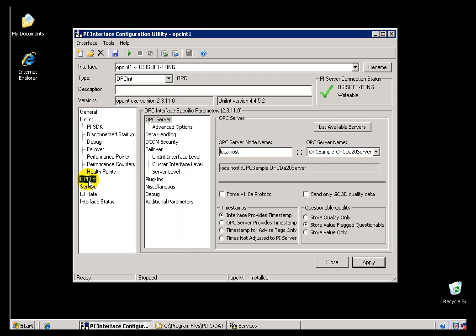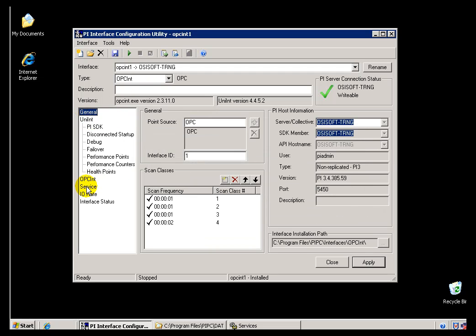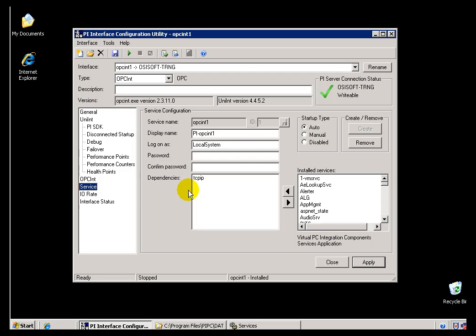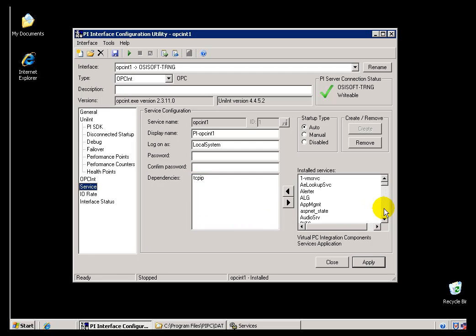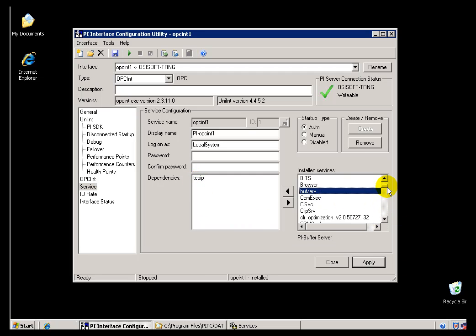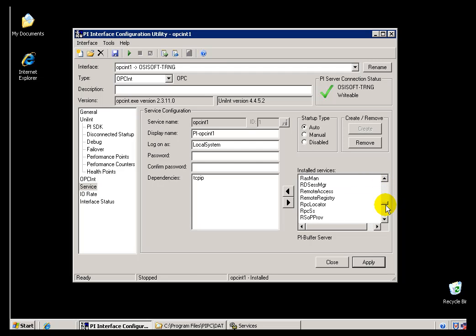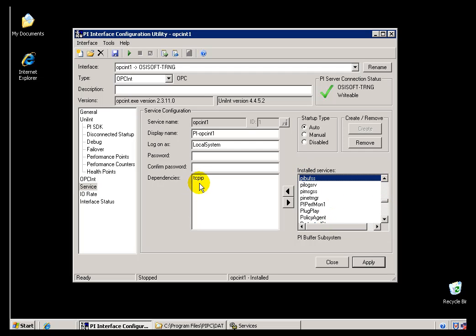If we take a look at the OPC interface and look at the Service section, you're going to want to add the PI Buffering Subsystem as a dependency. The Buffer Server is the service that uses the API. The PI Buffering Subsystem is the second of the two ways of doing it — depending on which one you're using, make sure this interface is dependent on that.